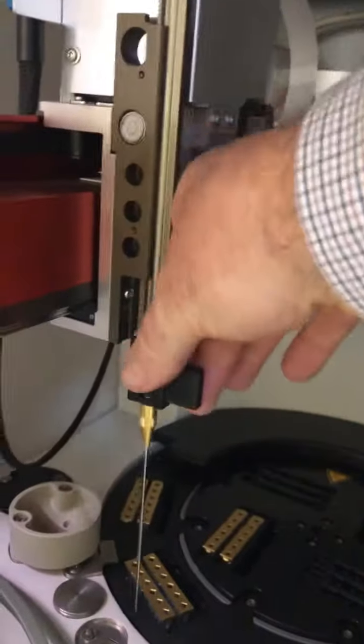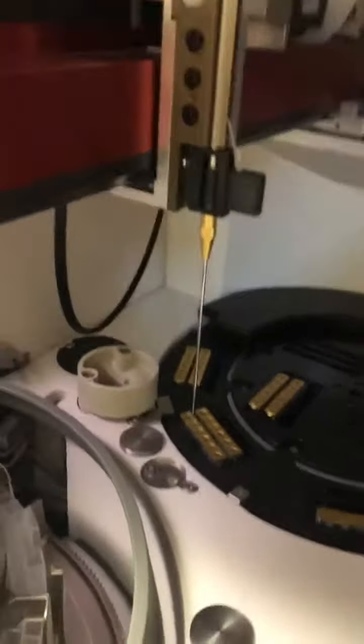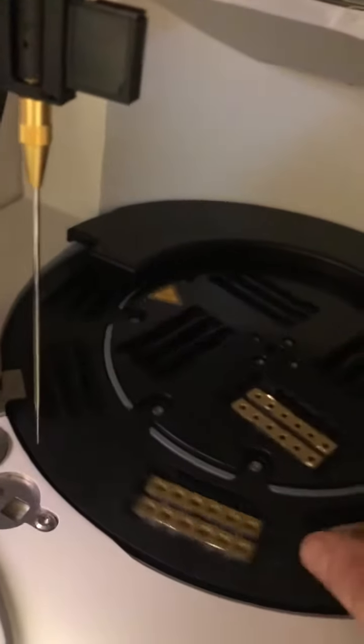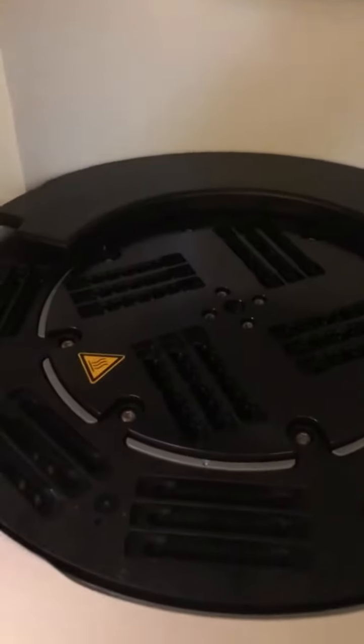My next thing is I'm going to open up the main cover and then I'm going to check all of my positions. So the first thing I'm going to check is the pipette arm and make sure that it is free to move. So it is free to move and free to move up and down as well. I'm going to check that the incubator position can move. So that's here. And while I'm at it, I'm going to remove these cards that are here. These are going to be wasted and dumped anyway. But by removing them, I speed up the initialization process. Okay, so that looks all okay. So I'm also going to check in case there's any dropped punching cards, which there isn't, so that's okay.